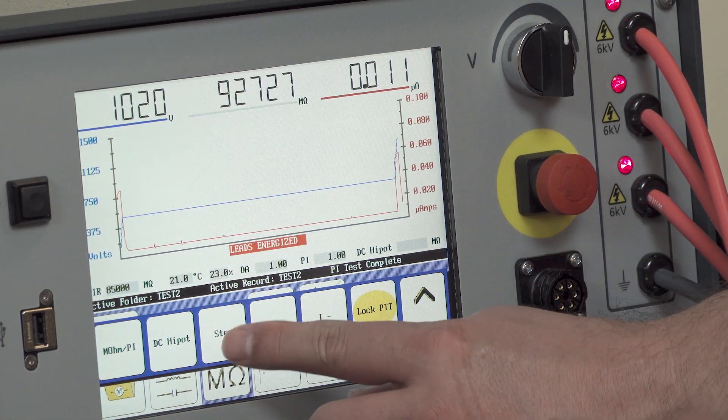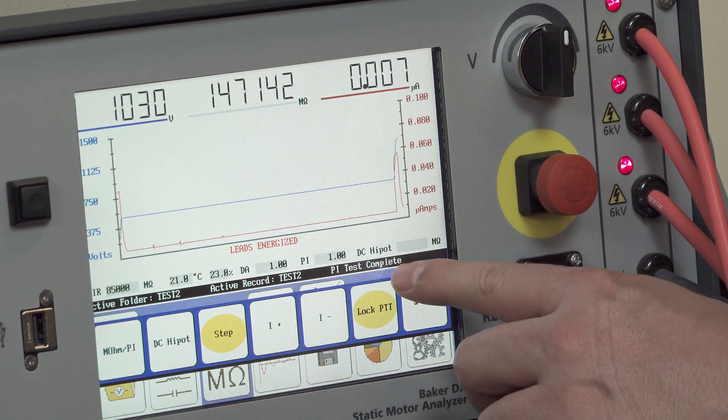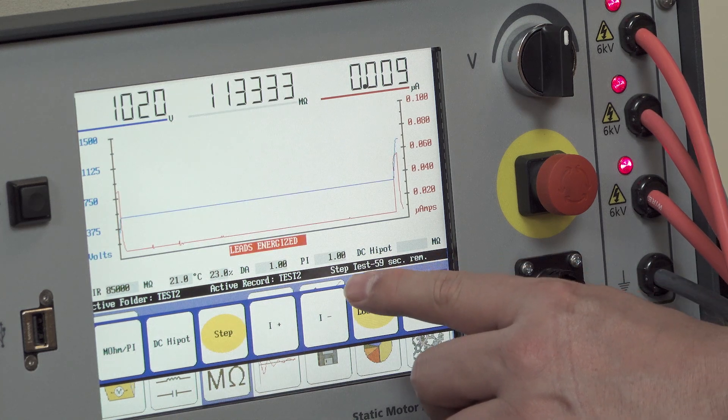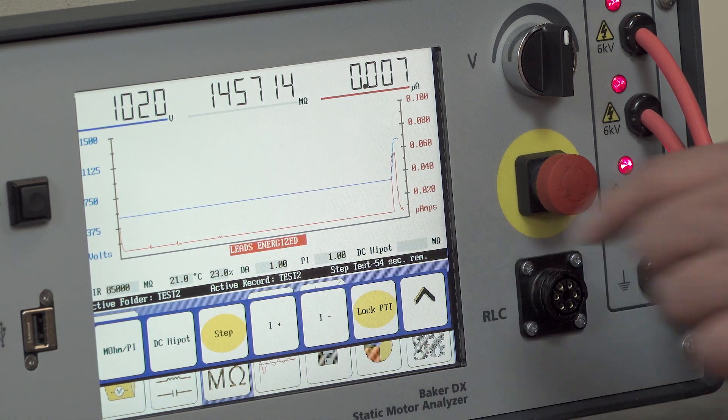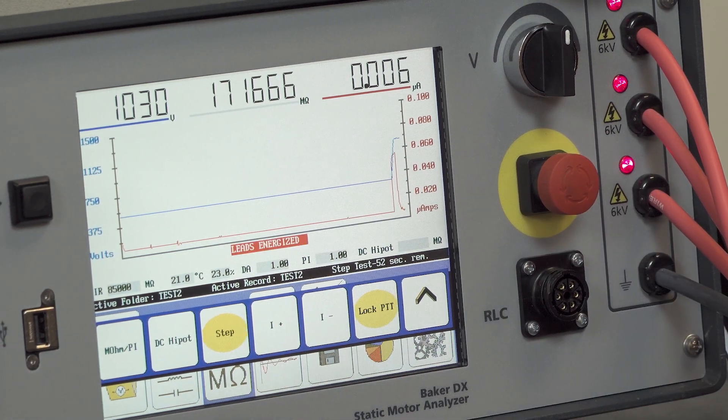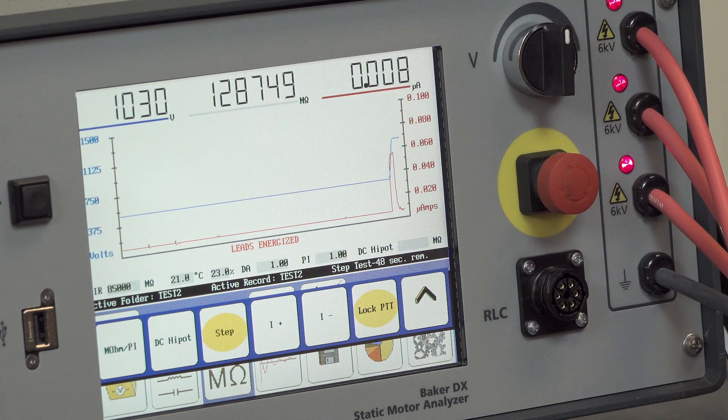So having achieved a thousand volts, in this case I'm doing a step voltage high pot, so I'm going to select step. That's going to start my step timer. On the right-hand side here now it says step test 57 seconds and counting as it's going to count down to zero and that step is complete. Then I'll proceed to the next step which would be 1500 volts.